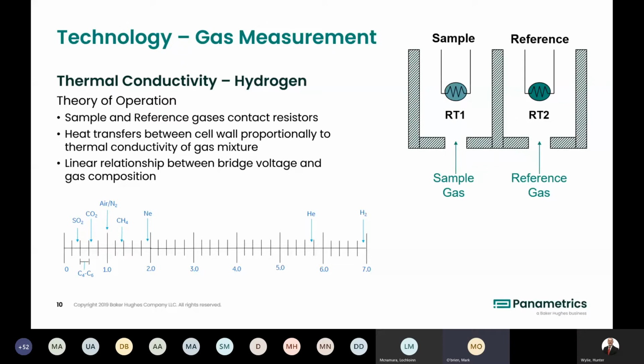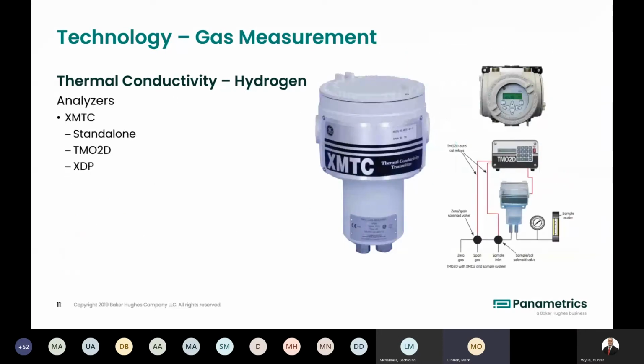So what we can use is the cooling effect that hydrogen will have with a given gas flow compared to a reference, so that could be air or something else. We can use that difference in cooling to create an electrical output. This electrical output can then represent the presence of hydrogen and corresponding concentration of hydrogen in that gas. Again, the package that this instrument can come in can be a weatherproof or X-proof, depending on your requirement. Again, it has the similar displays that the XMO2 has. Again, we can provide this with or without sample systems, and it has the required hazardous area certifications that are usually needed in this type of industry.